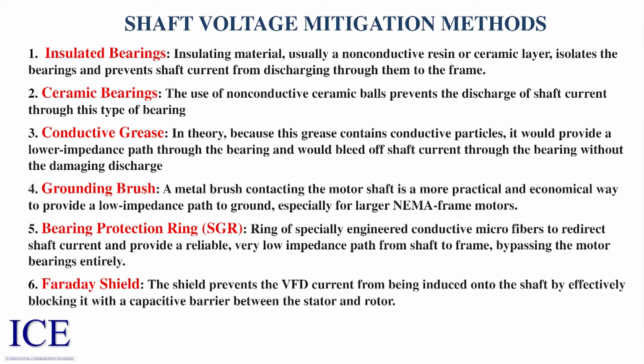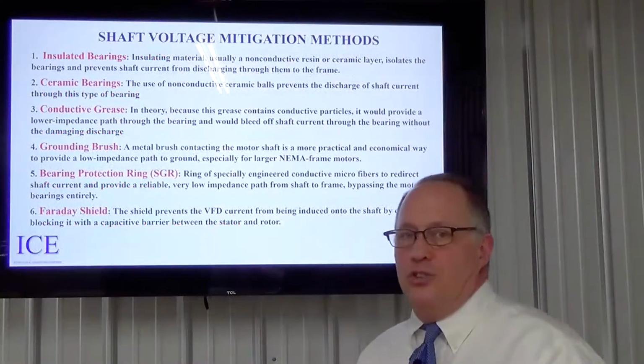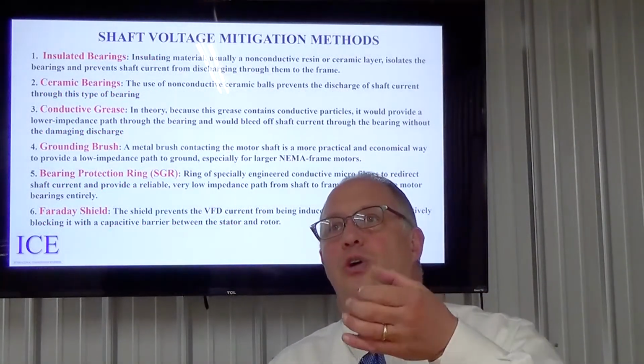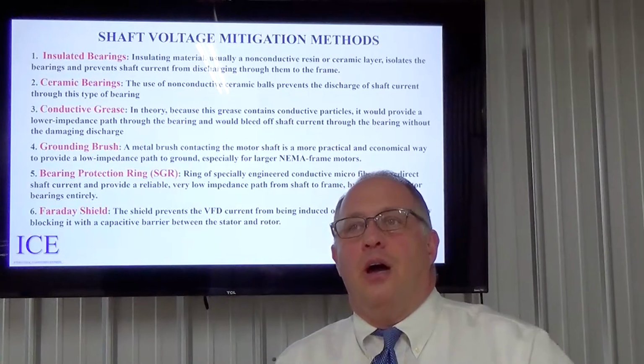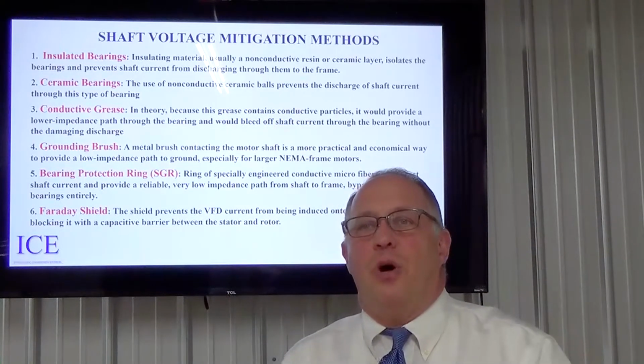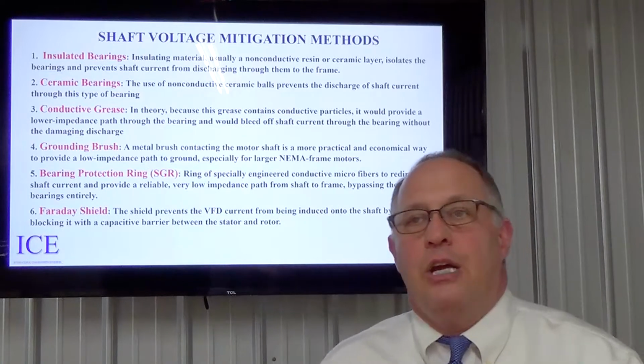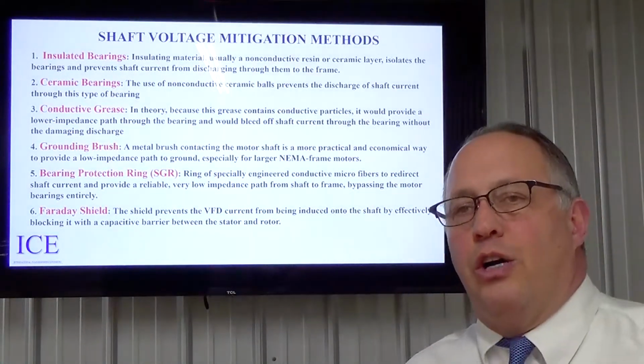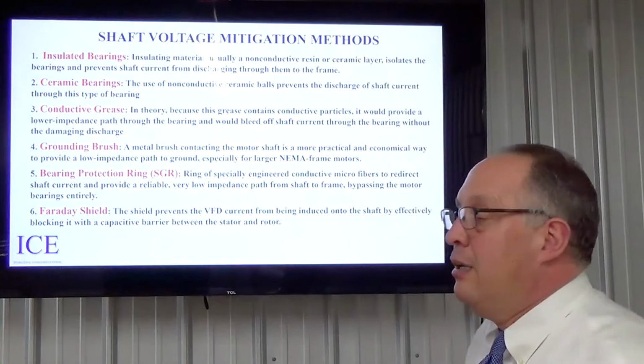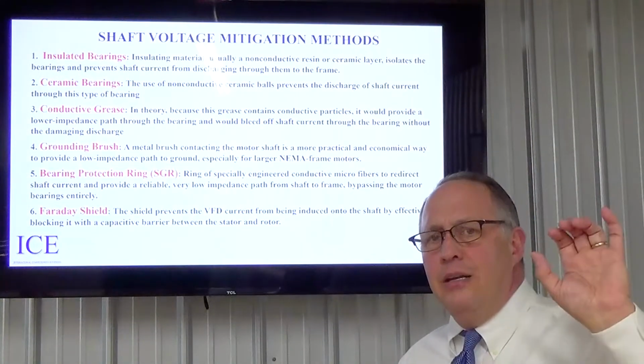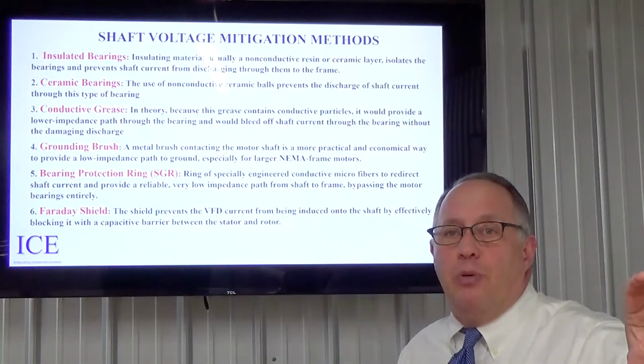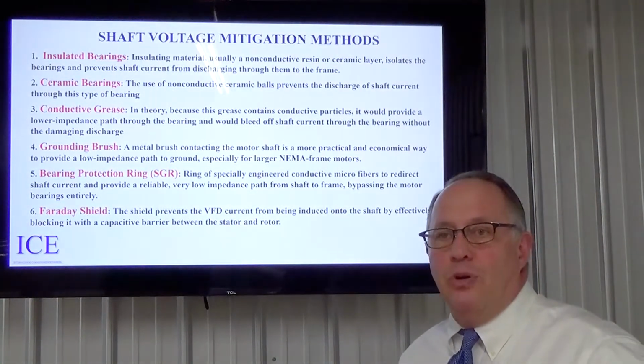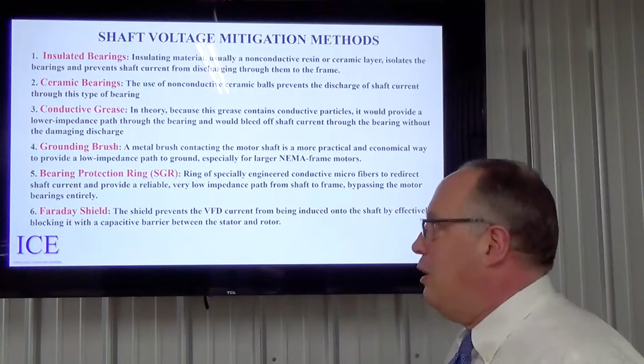In theory, because this grease contains conductive particles, it would provide a low impedance path through the bearing, which would bleed off the shaft current through the bearing without damaging discharge. In other words, you're essentially hooking a jumper across the bearing so that any shaft voltage jumps over and goes directly to ground. You don't have the buildup of voltage and the arc over, it just bleeds off to ground. In theory. Once again, if it's not kept lubricated properly, then that particular type of grease can overheat and you can still end up with the damage.